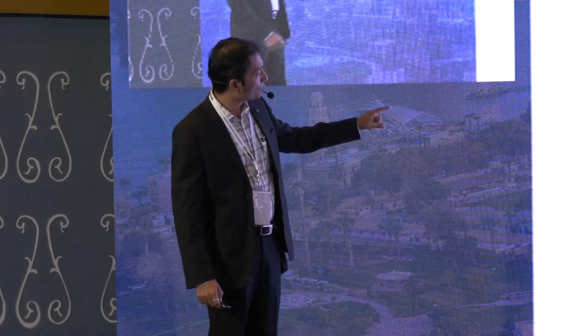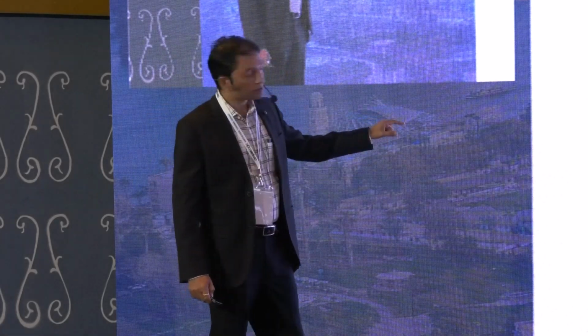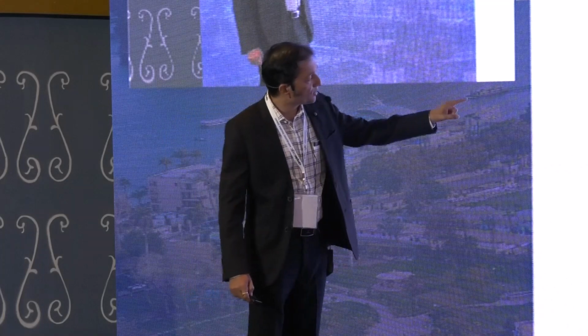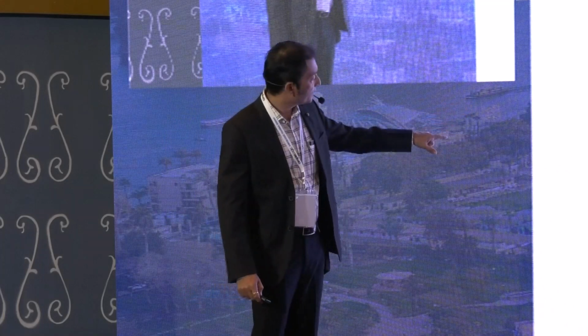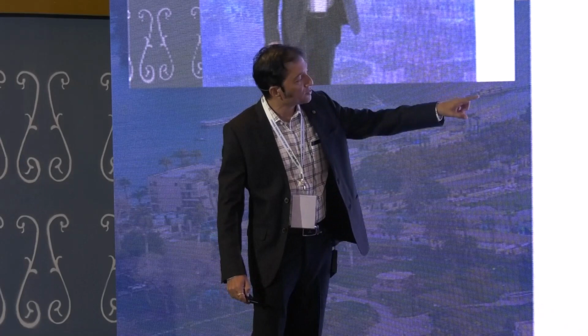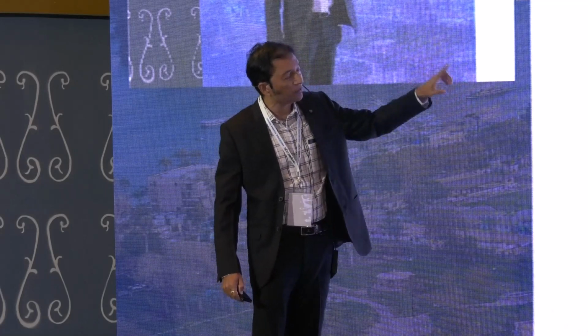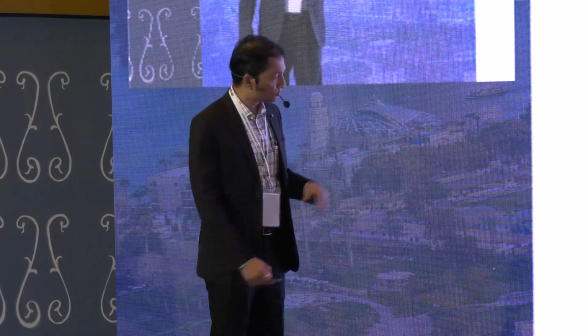At point number 2.3, the guidance tells you about the least burdensome approach. And it says that we believe we should consider the least burdensome approach in all areas of medical device regulation. So FDA allows you to think differently. But at the same time, it asks you to come back and tell your approach before you go for it.